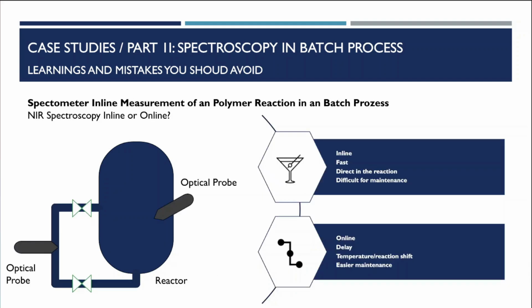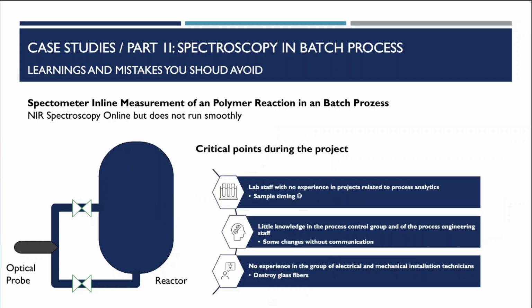So for the online conditions of the measurement, they were thinking about how to put this in a process. There was an idea to put it inline, or you can also do it online. Initially, it was done inline, which led to fast measurements and good results. Unfortunately, the window of the probe gets dirty from some reaction products, which causes the measurement to fail, because it was not possible to simply stop the batch process and take out the probe to clean it. So we decided afterwards to put it online, which is more complex with a bypass and a pump, but it allowed us to clean the probe during the process.